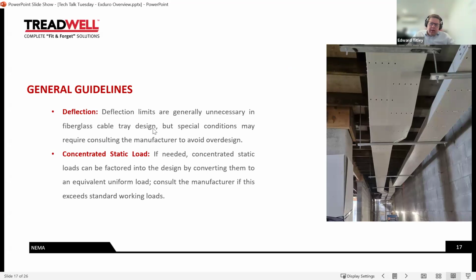A couple of details though. Typically, deflection limits are not considered in the design of FRP cable ladders unless there's a specific requirement around deflection. And in that case, happy to talk to you about this with you. So the deflection you'll see in the cable ladder at the rated and working loads. However, typically it's not necessary because with FRP, typically we're limited by deflection rather than strength. So hence in a cable ladder application to prevent over design, typically we design to strength. The NEMA standard requires a safety factor of 1.5 as a minimum, so that's what we work to.